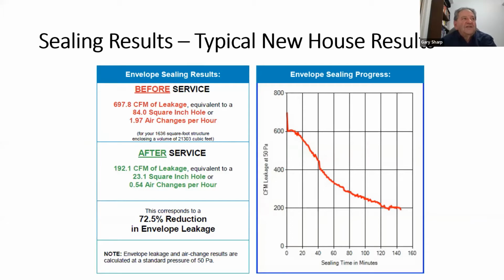That is equivalent to an 84 square inch hole. So imagine a hole that is basically 8 by 10. And the house tested at 1.97 air changes per hour. That's really good. That builder was paying a lot of attention to detail. He had the house quite tight compared to building code type houses that are being built in Canada now.